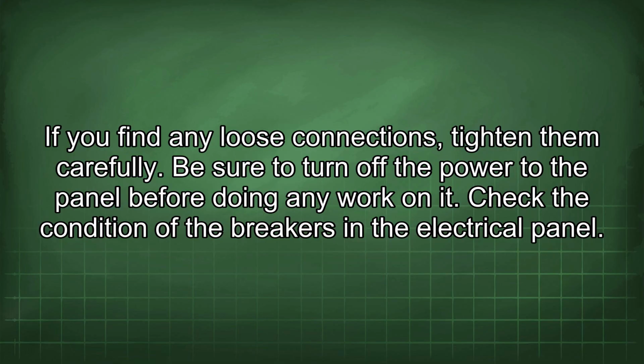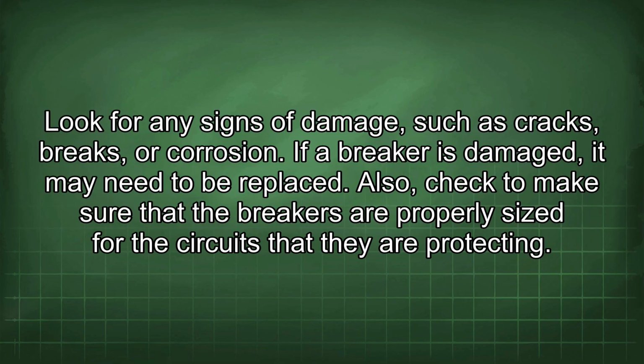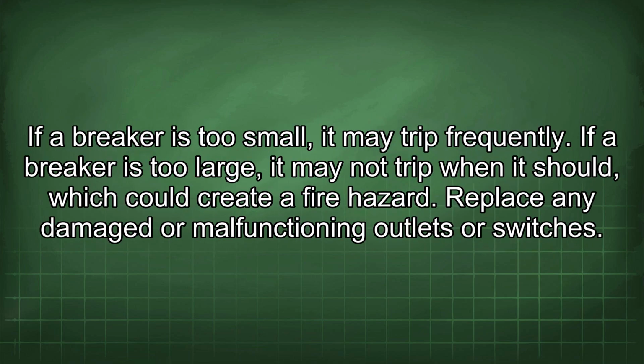Check the condition of the breakers in the electrical panel. Look for any signs of damage, such as cracks, breaks, or corrosion. If a breaker is damaged, it may need to be replaced. Also, check to make sure that the breakers are properly sized for the circuits that they are protecting. If a breaker is too small, it may trip frequently. If a breaker is too large, it may not trip when it should, which could create a fire hazard.